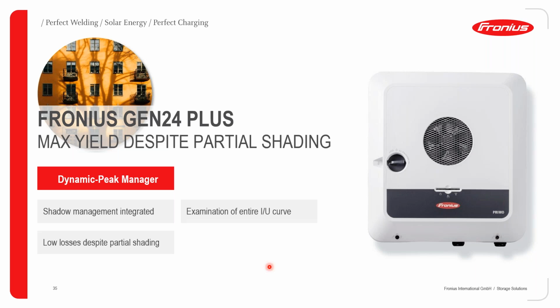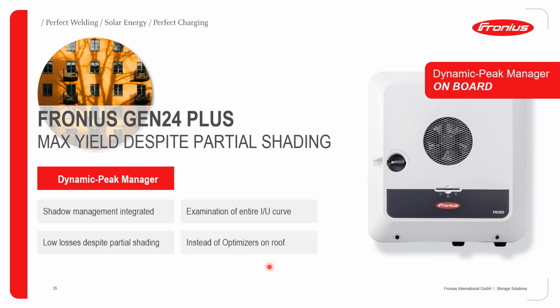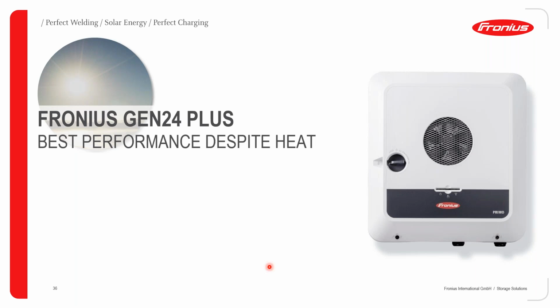This happens by the PV inverter using the dynamic peak manager integrated in the MPPT algorithm, which is able to examine the entire IV curve of the array from time to time. With the Fronius inverters this happens every 5 to 10 minutes. Therefore, this is a better proposition, even in terms of reducing capex when you are considering your installation. Because the alternative, if you don't have a dynamic peak manager to manage shading conditions, would be to install a system with optimizers. So the dynamic peak manager integrated in the Fronius inverters offers you a better proposition than the use of optimizers. Optimizers increase the risk of failures in the system, but this is a topic that we can go into in another webinar.